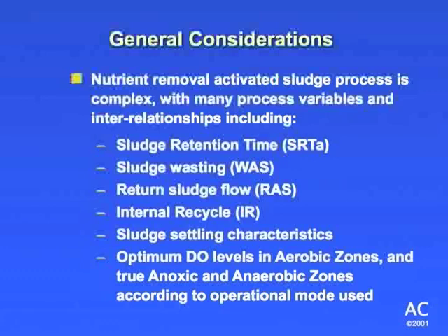Yeah, but what's causing you to get the return, and again, this is the part that drove me nuts, when it's like, why do I get the anoxic zone there? I've got to nitrify. Well, stuff that has not been nitrified is passing through there. Some of it's being taken up, okay? Because you always are going to have some uptake. Remember we talked in the earlier class, some of your nitrogen's being removed just for metabolic reasons, okay? But it's not a significant portion.